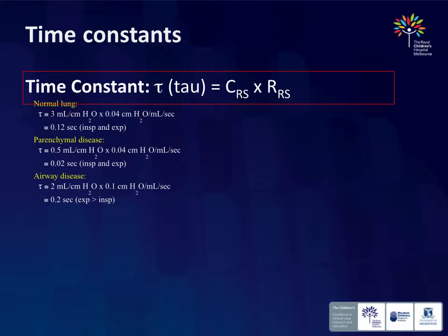And we'll talk maybe in the lab and in the workshops about what normal compliance settings are and abnormal compliance settings. So compliance is low. Gas will get there quickly, and if you give enough pressure, you actually move the alveolus very quickly. So consequently, our time constant, the product of compliance and resistance, is very short. So we don't need much time to move that one. So an I time here of as little as 0.1 to 0.2 second may be adequate to move an alveolus with HMD. And consequently, you can see we now have a much shorter I time than we would in a term baby being ventilated for whatever reason.